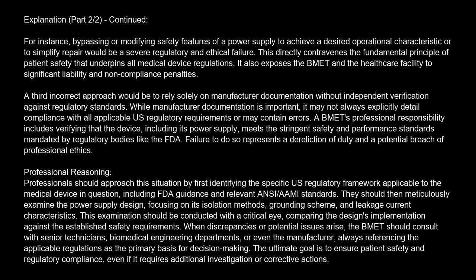Professional reasoning. Professionals should approach this situation by first identifying the specific U.S. regulatory framework applicable to the medical device in question, including FDA guidance and relevant ANSI/AAMI standards. They should then meticulously examine the power supply design, focusing on its isolation methods, grounding scheme, and leakage current characteristics. This examination should be conducted with a critical eye, comparing the design's implementation against the established safety requirements. When discrepancies or potential issues arise, the BMET should consult with senior technicians, biomedical engineering departments, or even the manufacturer, always referencing the applicable regulations as the primary basis for decision-making. The ultimate goal is to ensure patient safety and regulatory compliance, even if it requires additional investigation or corrective actions.